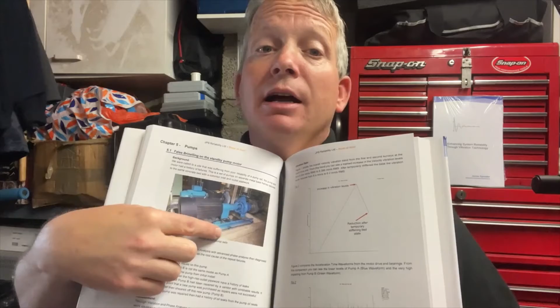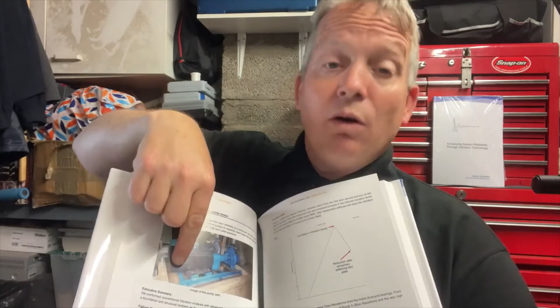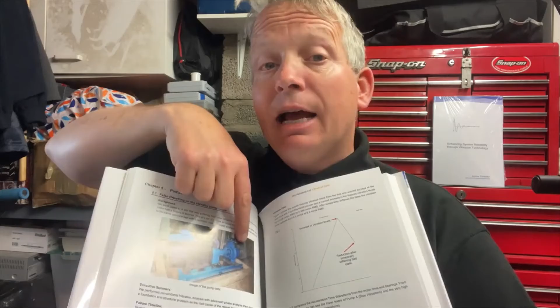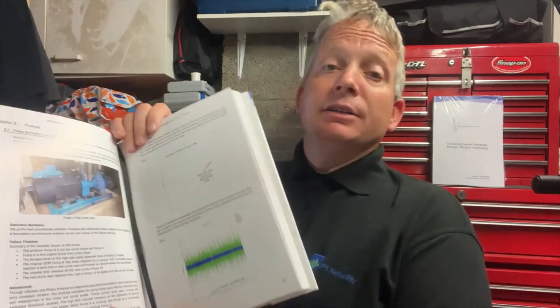You can see here, it's got the two pumps next to each other on a common metal frame, unfortunately, and they feed through to a common header system which comes out. So you can imagine the pump - if one pump's running and one's not, obviously you've got your valve where the two pipes come together to go straight up to the vertical riser. So the pump running creates pump vibration which transfers to the other pump, and that comes back to the motor, which is what we're looking at in the vibration data, the outer race defect.